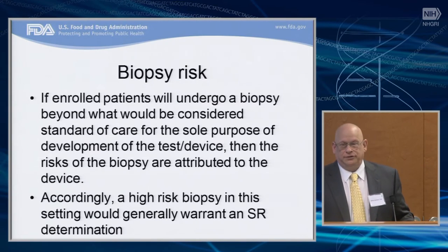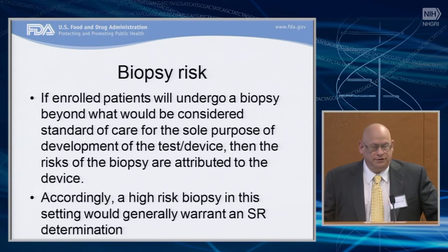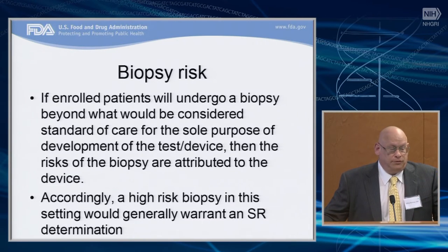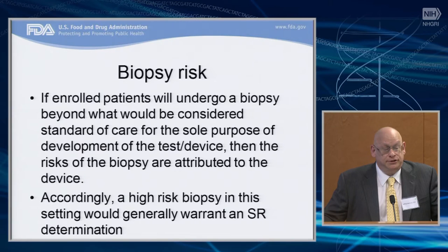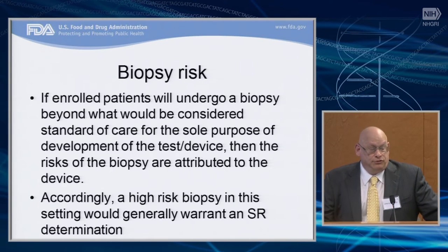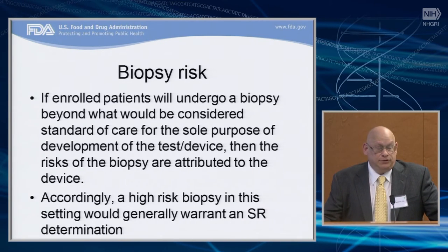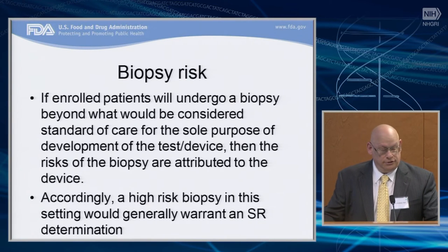Okay, biopsy risk. This can be a complicated question, but it's important to recognize that if enrolled patients in a trial will undergo a biopsy beyond what would be considered standard of care for the sole purpose of development of the test or the device, then the risks of the biopsy are attributed to the device. So accordingly, a high-risk biopsy in this setting would generally warrant a significant risk determination.